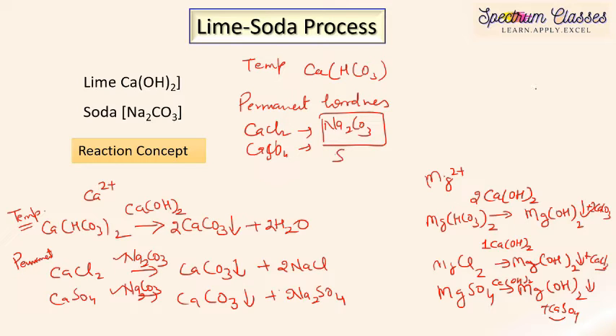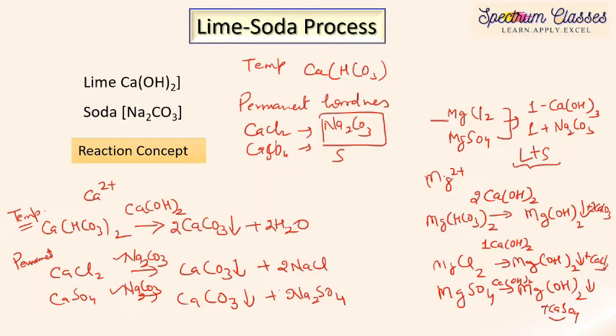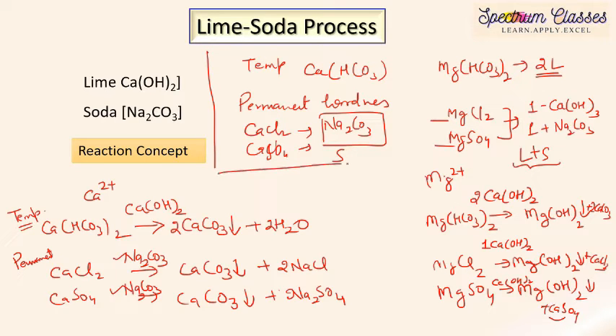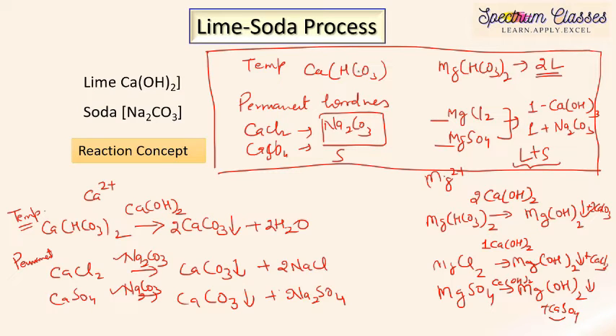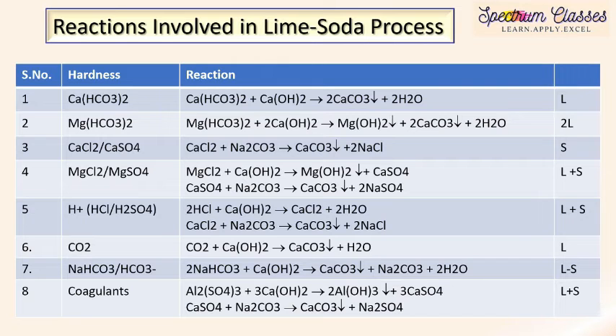For temporary hardness (calcium bicarbonate), one mole of lime is required. For temporary magnesium bicarbonate, two moles of lime are required. For permanent hardness — calcium chloride or calcium sulfate — one mole of soda is required. For permanent magnesium hardness — magnesium chloride or magnesium sulfate — one mole of lime and one mole of soda are both required. This is the key rule to remember for solving numericals.